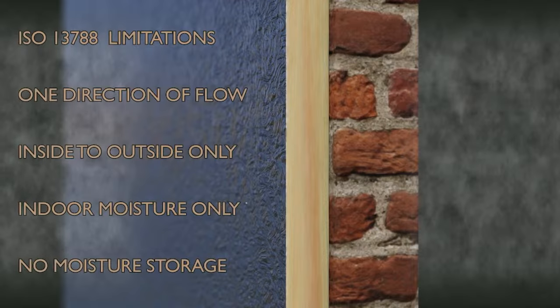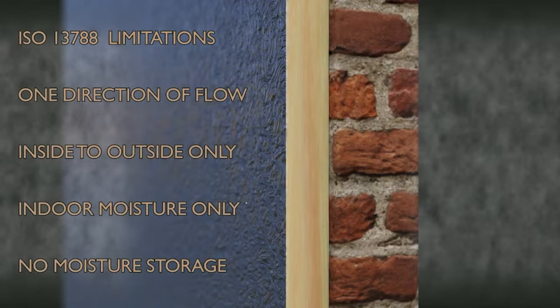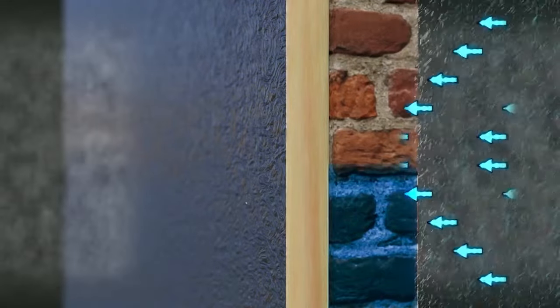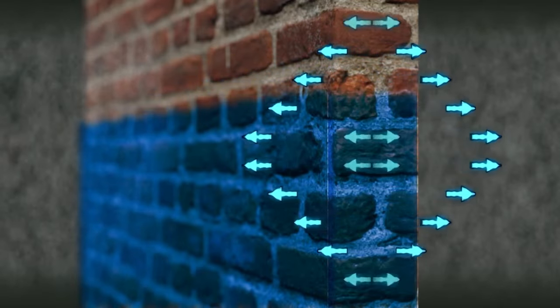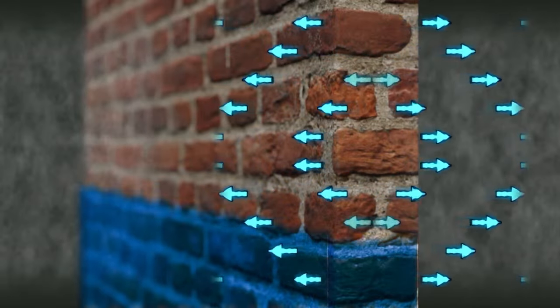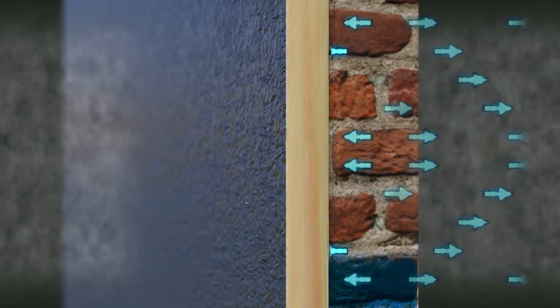The Glaser method in ISO 13788 assumes moisture only flows from inside to outside and that the indoor environment is the only source of moisture. It also omits the ability of the building fabric to store and release moisture. For most building types these omissions don't significantly affect the result, but in solid walls they can play a greater role. In a solid wall, moisture from rainfall is absorbed directly by the wall and stored until it dries out.